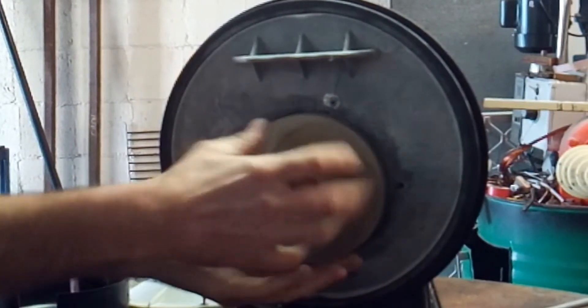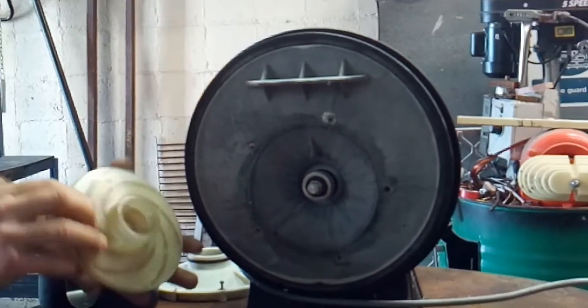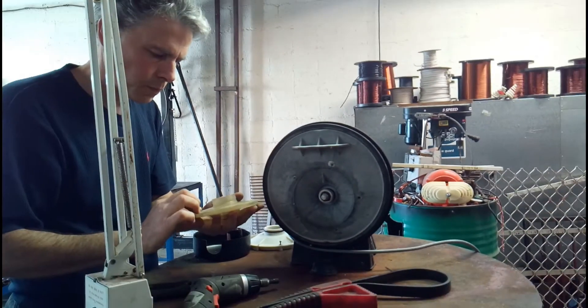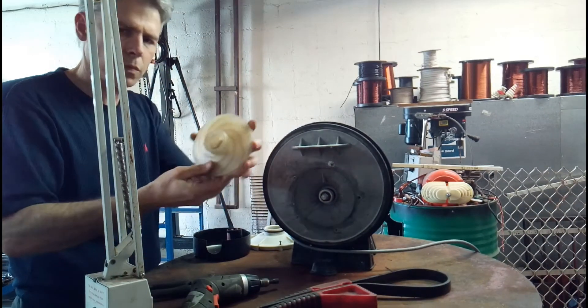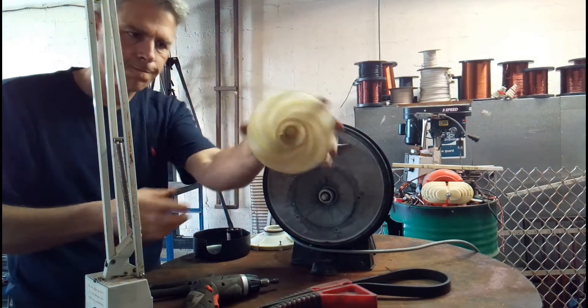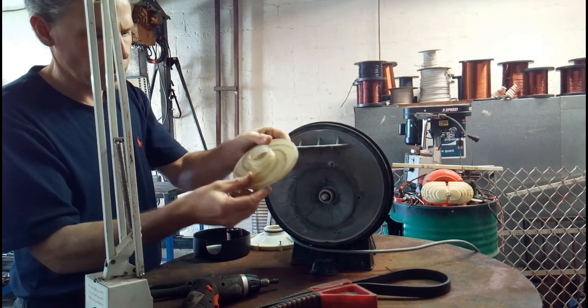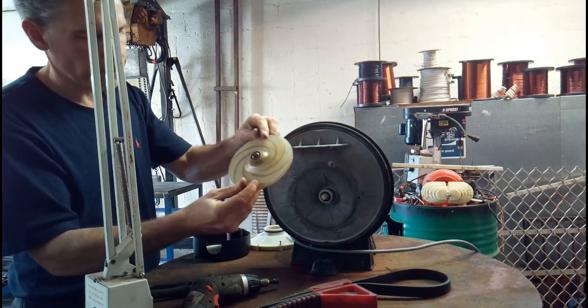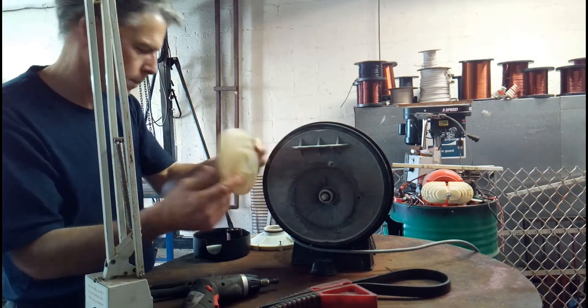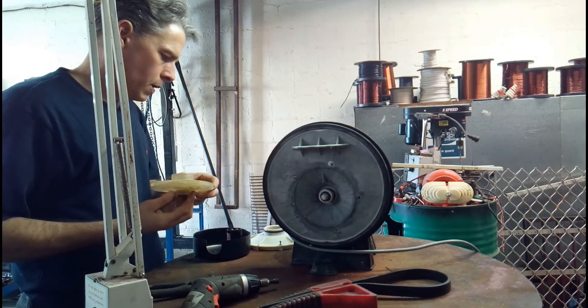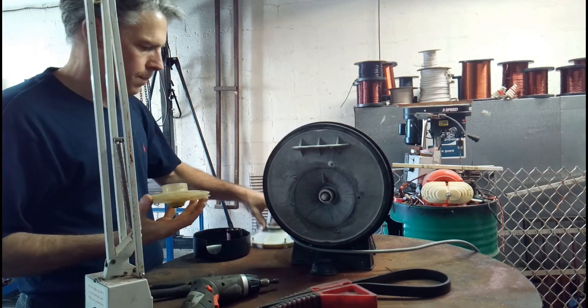Things to look for when you get the impeller off. Quite often they can fracture in the centre, and if you hold them up to the light you can often see just how bad they are. Also check the metal boss where the thread is.